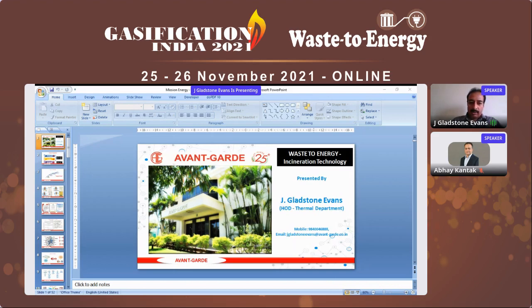Similarly, if you go for more than 1,200 TPD, we can go for 3 boiler and 1 TG configurations. People normally don't go for 2 boiler, 2 TG, but in certain countries abroad, they go for this configuration also. Then this is the power generation from the waste to energy plant. Roughly, from a 300 TPD plant, you can generate 4 to 6 megawatt of power, depending on the calorific value. From 450 TPD, 6 to 8 megawatt; 600 TPD, 8 to 12 megawatt; 750 TPD, 10 to 14 megawatt. People go for either 1 into 750 or 2 into 600, and normally these are repeated in multiples of these capacities.